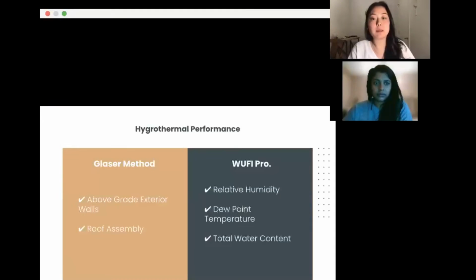Also, as previously mentioned, this is the method of analysis that was used to determine the moisture penetration problem that we had with the originally designed cold roof assembly. Regarding the WUFI Pro analysis, the properties analyzed were the total water content, the relative humidity, and the dew point temperature. The total water content of both assemblies did not surpass 20 kilograms per meter squared, and the relative humidity never reaches 100% within the assembly. However, there was indication of moisture on the exterior surfaces, which is reasonable due to direct contact with the exterior environment. Lastly, the dew point temperature does not exceed the temperature within the assembly, indicating a low risk of condensation throughout.